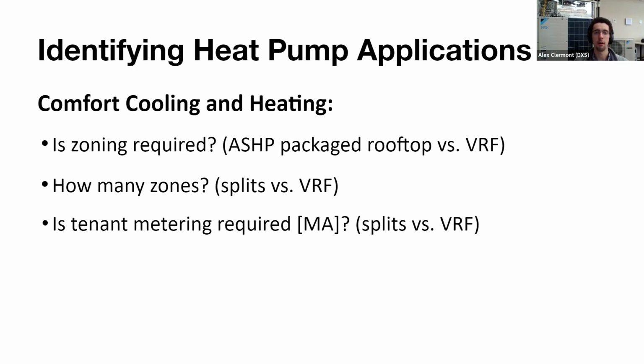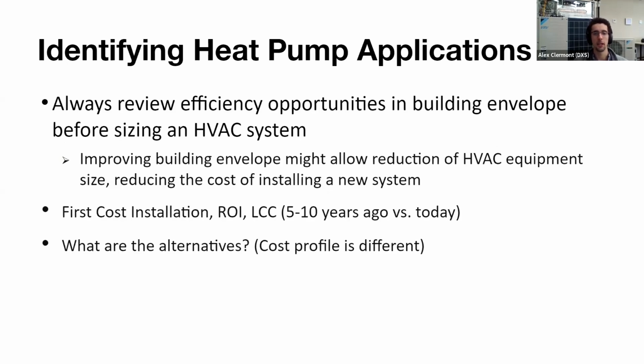So, one thing with these heat pumps is we love them. They're great. We think it's the most efficient way to deliver BTU to spaces, but they do work best when combined with good envelopes. The first part of a building you should try to fix is your envelope, and then you can look at improving your heat pump or adding a heat pump. In terms of cost, 5 or 10 years ago, there were some alternatives that were much cheaper, such as gas-fired furnaces or electric baseboard, and that gave VRF the reputation of being quite expensive. That has changed. We've seen the price of VRF come down quite a bit over the past 10 years or so. There's a lot of it going on, and a lot more trained contractors that are very comfortable with this technology. So if you do want an all-electric building or a low-carbon building, the alternatives are at least as expensive as doing VRF.